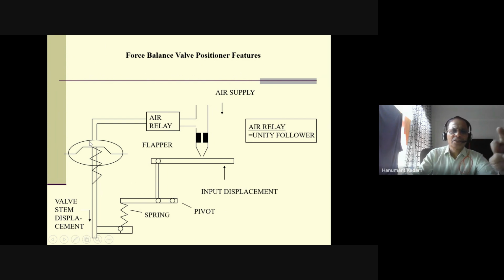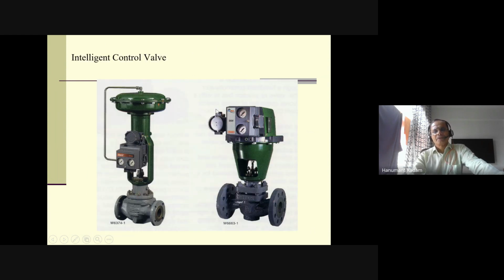So you can see here, this is a valve stem. This is the link. It is through a spring. It is connected to the pivot, and input displacement of this across the nozzle, and air supply, back pressure is generated. So this is the valve here.